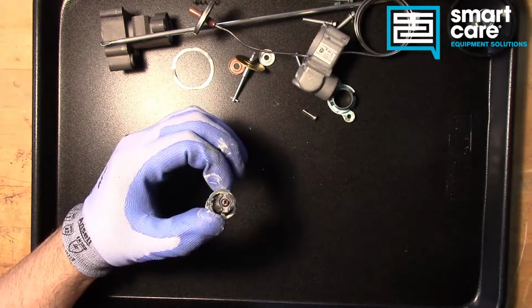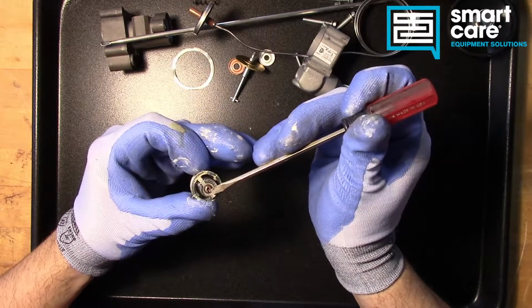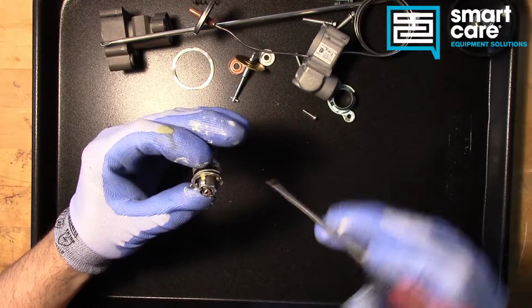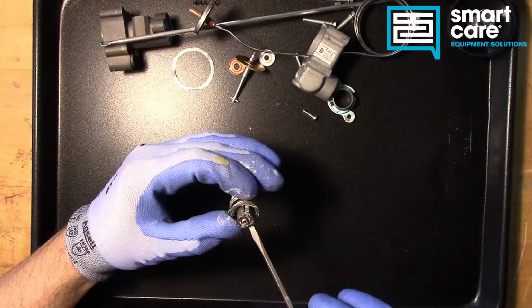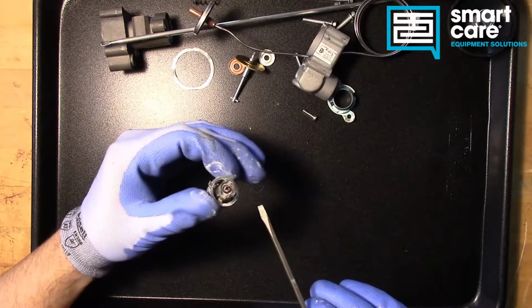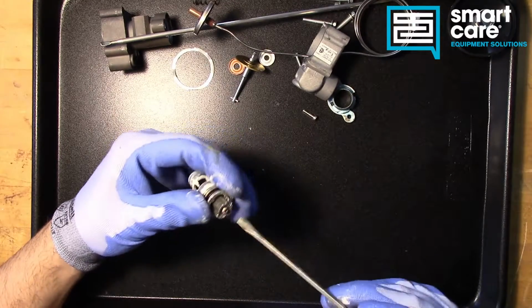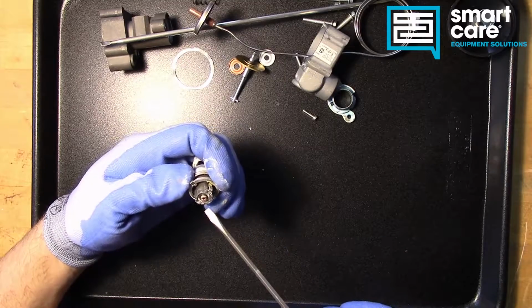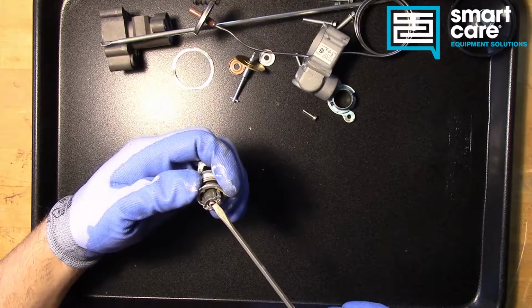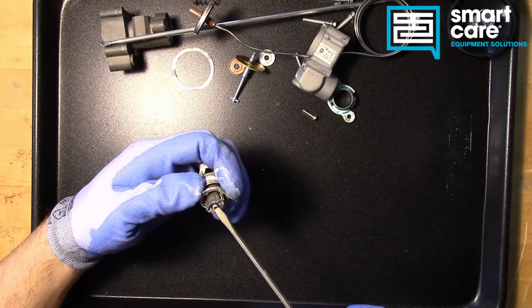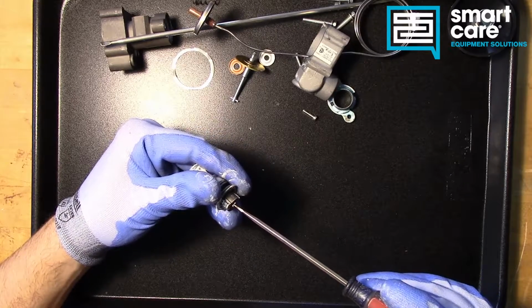Alright, so the calibration screw is a really thin slotted screw, and it's got a dab of nail polish on it. You'll see this in all different colors. Could be red, could be green, could be yellow, whatever nail polish they had at the factory that day. And typically before you go to adjust this, you've got to put a little dab of nail polish remover in there to get it loosened up.